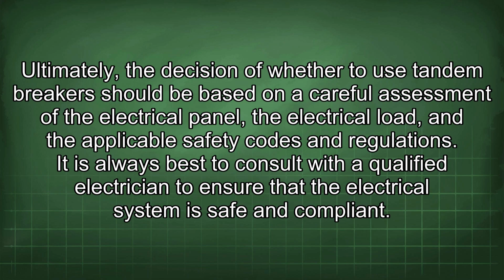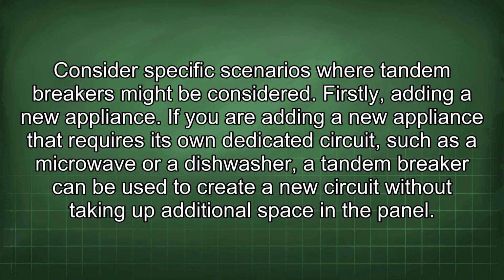Ultimately, the decision of whether to use tandem breakers should be based on a careful assessment of the electrical panel, the electrical load, and the applicable safety codes and regulations. It is always best to consult with a qualified electrician to ensure that the electrical system is safe and compliant. Consider specific scenarios where tandem breakers might be considered. Firstly, adding a new appliance. If you are adding a new appliance that requires its own dedicated circuit, such as a microwave or a dishwasher, a tandem breaker can be used to create a new circuit without taking up additional space in the panel.